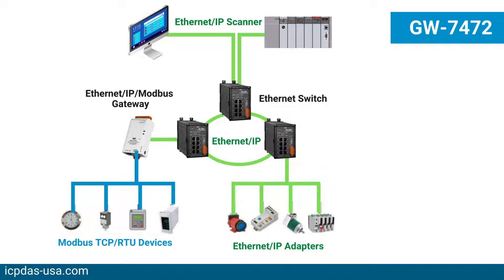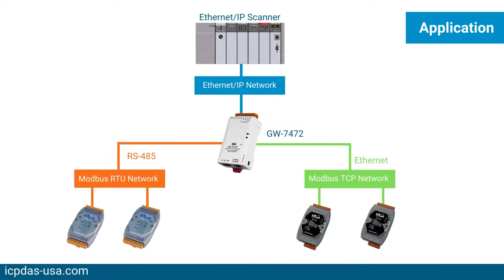The output data transmitted by the EtherNet/IP scanner is updated to the registered data of Modbus RTU slaves and Modbus TCP servers via the GW7472. These modules can also scan or map registered data from EtherNet/IP devices in exchange with Modbus registers.